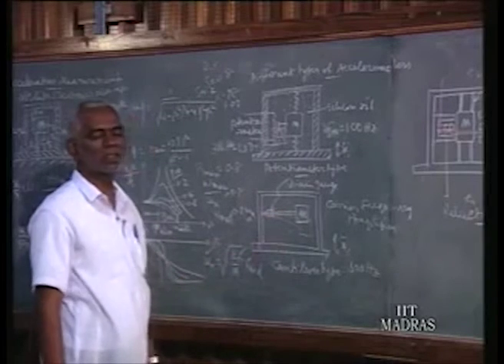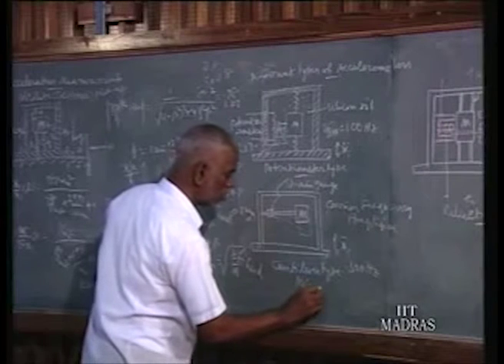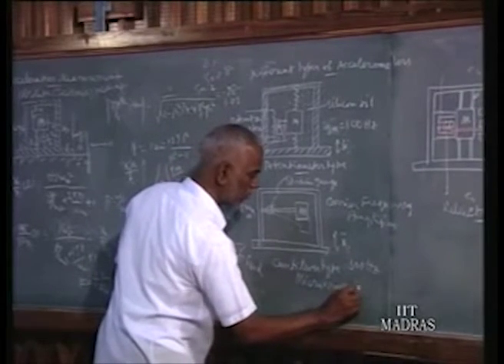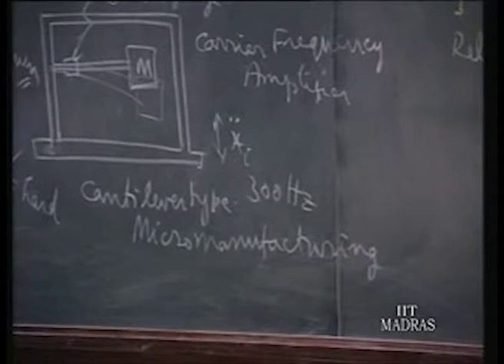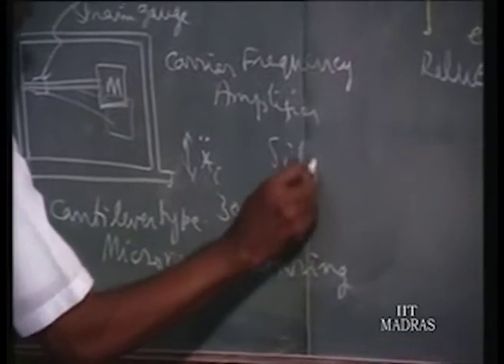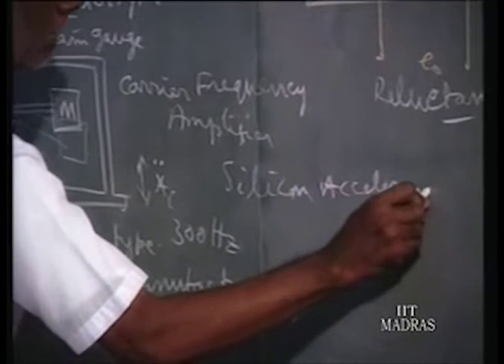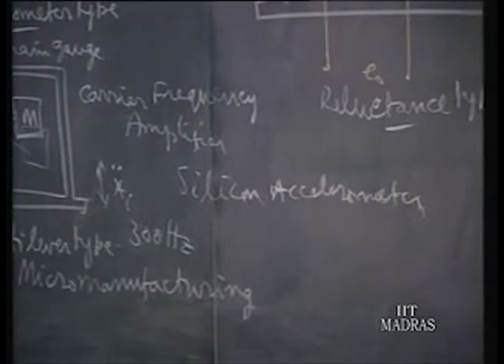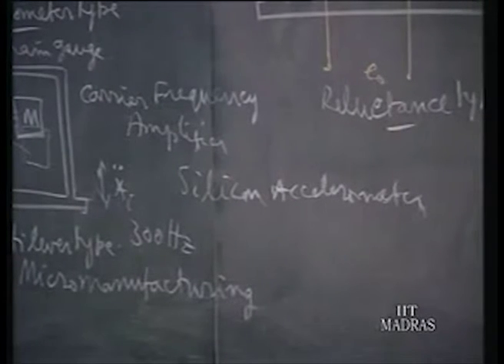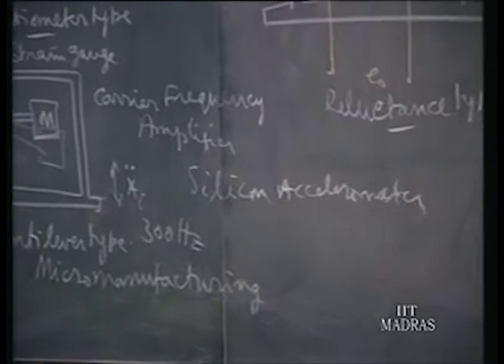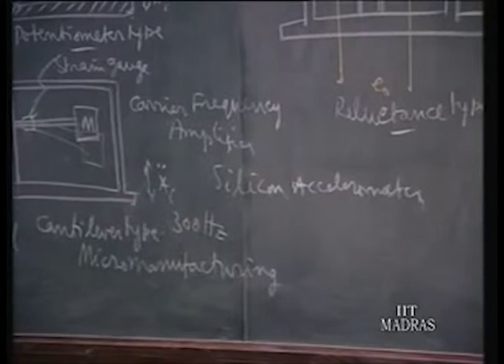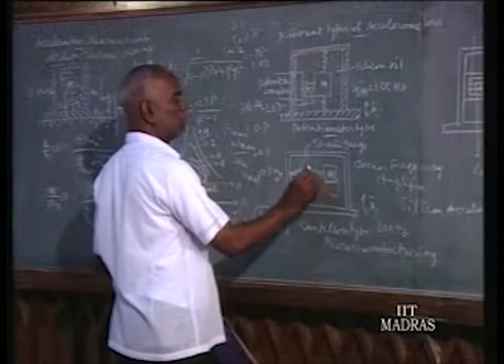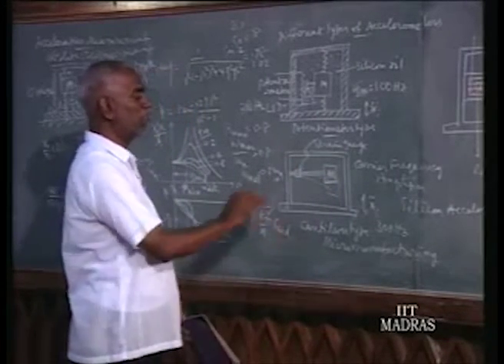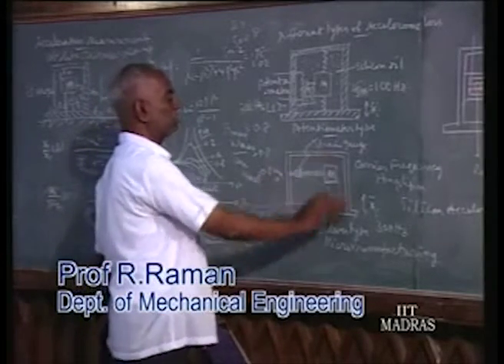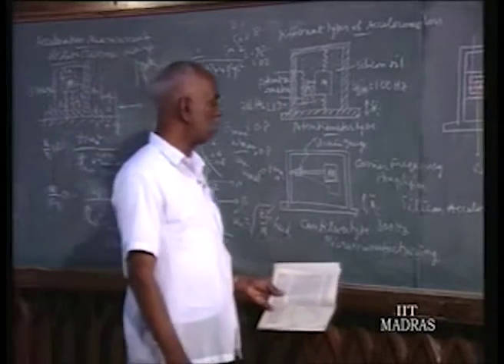Now this type of construction is suitable for micro manufacturing. We have mechatronic components, the so-called silicon accelerometer. The whole accelerometer may be within a few mm square. That is called micro manufacturing, and it is obtained using lithography and photo etching principles. From the silicon crystal itself, the whole mass and the lever are made, and the strain gauge will also be made of silicon. That is amenable to micro manufacturing, rather than the other type. That is the speciality of this cantilever type of construction.